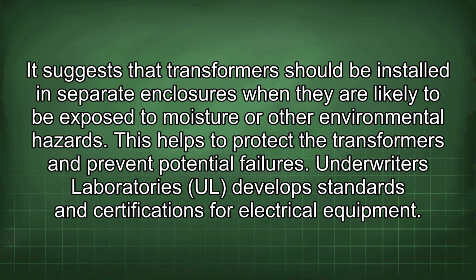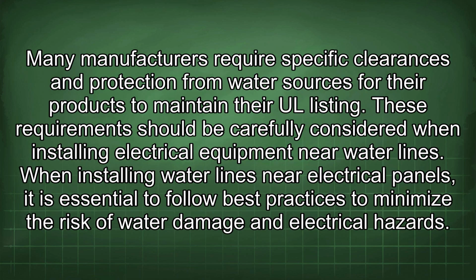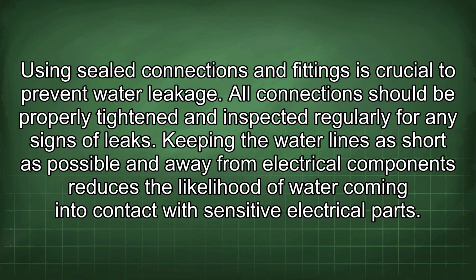Underwriters Laboratories, UL, develops standards and certifications for electrical equipment. Many manufacturers require specific clearances and protection from water sources for their products to maintain their UL listing. These requirements should be carefully considered when installing electrical equipment near water lines. When installing water lines near electrical panels, it is essential to follow best practices to minimize the risk of water damage and electrical hazards. Using sealed connections and fittings is crucial to prevent water leakage. All connections should be properly tightened and inspected regularly for any signs of leaks.